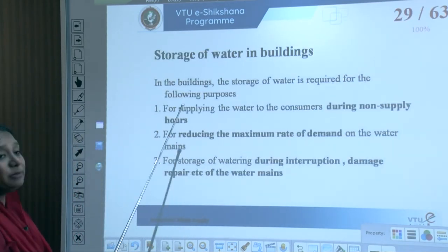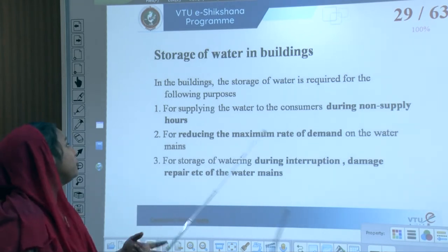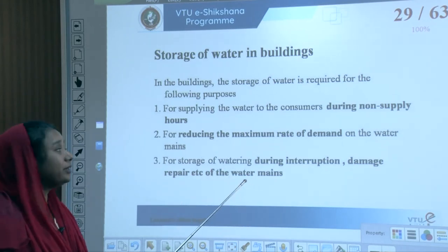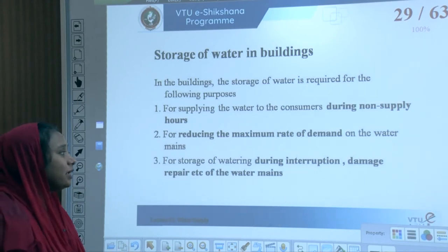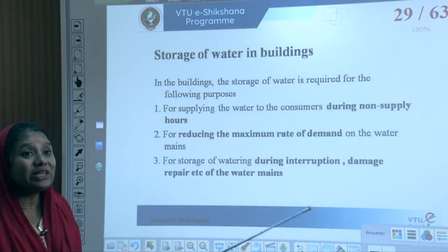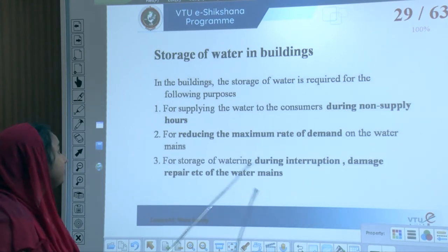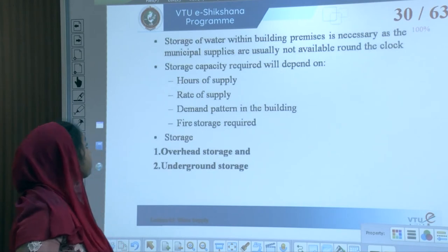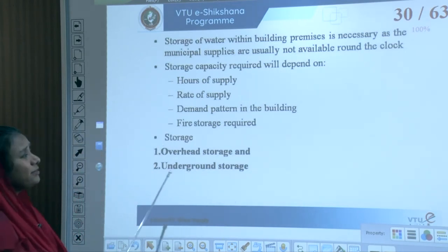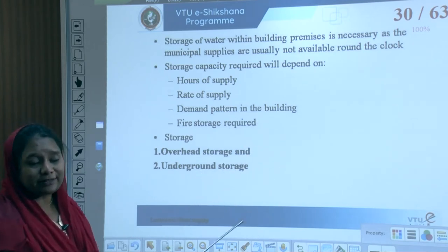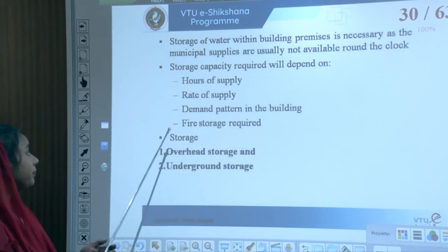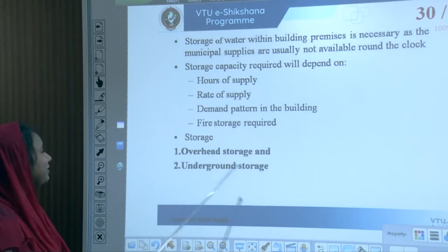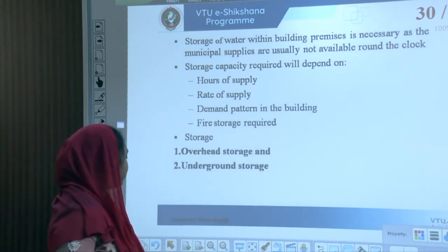Storage of water in buildings is required for three purposes: to supply water during non-supply hours, to reduce the maximum demand rate of the water mains, and to provide for emergencies such as interruptions or damage. Storage capacity depends on hours of supply, rate of supply, demand pattern of the building, and fire storage requirements — whether overhead or underground storage is used.